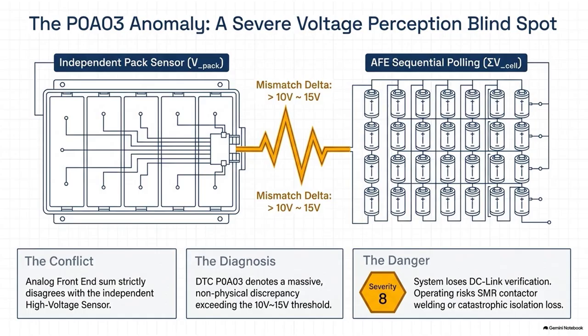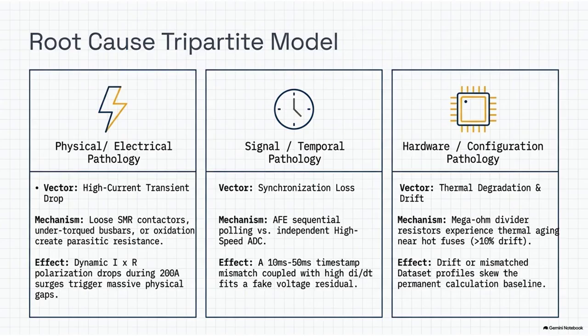Exactly. Or consider a physical failure on the AFE itself. The system is correctly configured for 96 cells. The physical box has 96 cells, but a single channel on one of the multiplexers burns out. Right. The chip simply skips that cell and reports the sum of 95 cells. In all these scenarios, whether it's the wrong software profile, a thermally baked resistor, a 50 millisecond latency gap, or microscopic oxidation on a bolt, the end result is identical. The total voltage does not equal the sum of the parts.